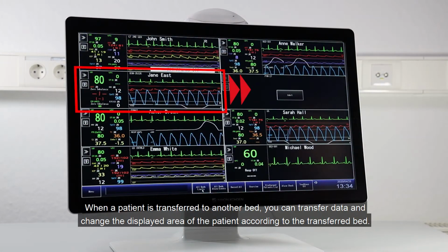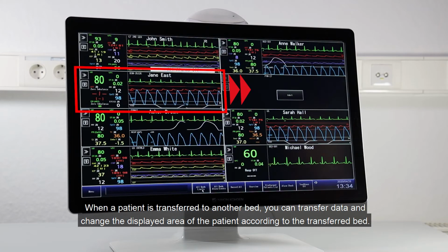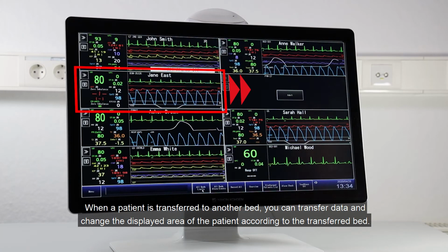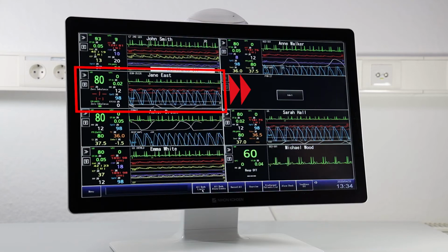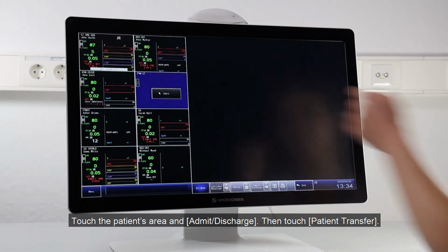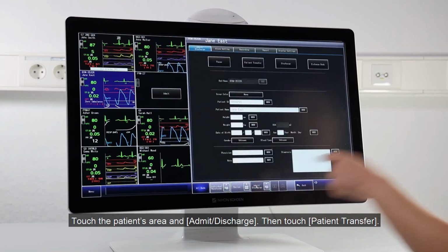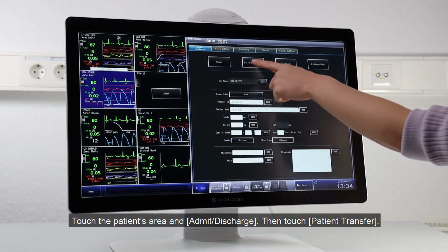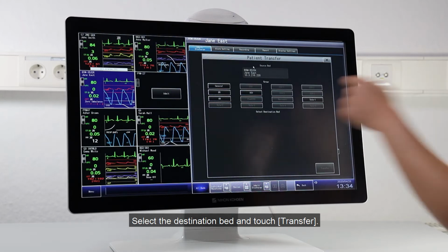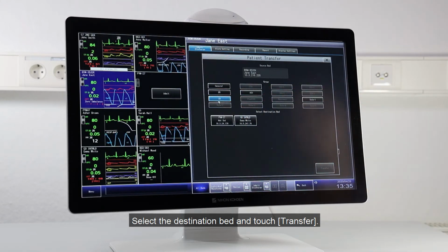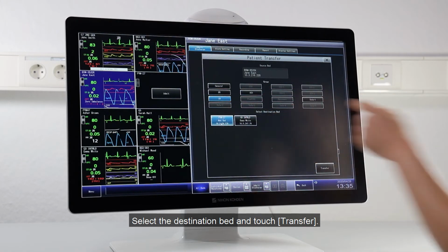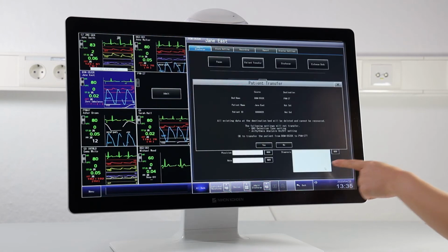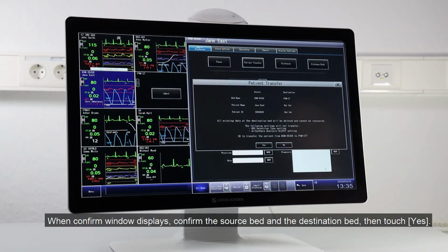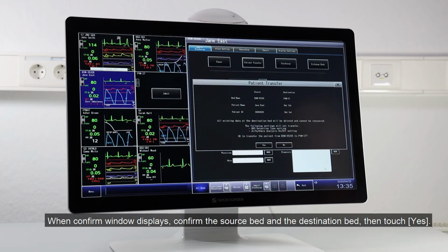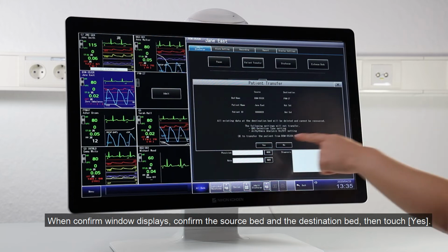When a patient is transferred to another bed, we can transfer data and can change the area according to the transferred bed. Touch the patient's area and touch Admit Discharge. Then, touch Patient Transfer. Select the destination bed and touch Transfer. When the Confirm window displays, confirm the source bed and the destination bed. Then, touch Yes.